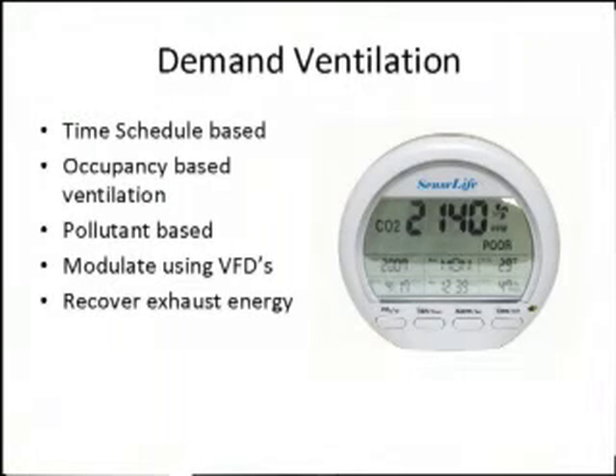These are some means that we can control ventilation in our commercial buildings. And the first one is a time schedule. So if we had that building that we saw on the last slide, we could have the schedule set by a thermostat or something that cuts it off at 5 o'clock, or reduces it to half or something. That would be the example of a time schedule. Just running off a simple time clock can be very effective. But the problem with that is it's not adaptive. When you do change your schedule, or people do have to work late, it doesn't really adapt to the facility very well.